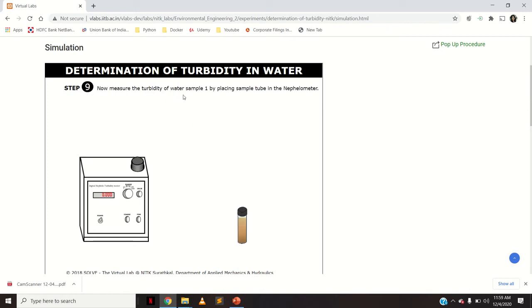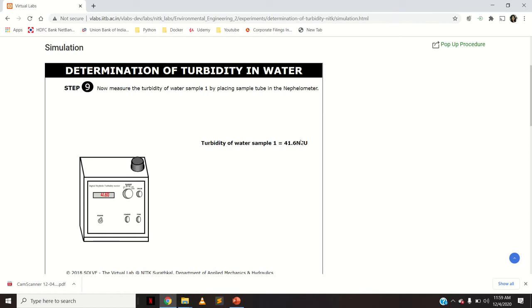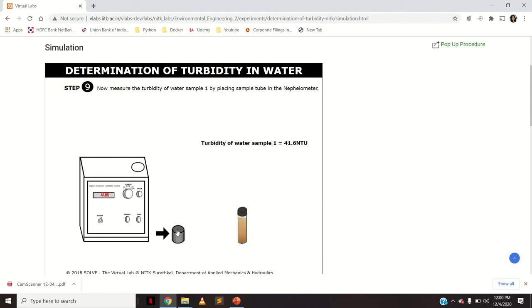Now measure the turbidity of the first water sample by placing the sample tube in the nephelometer. Since the instrument is calibrated with 0 NTU (distilled water) and 100 NTU (standard solution), open the lid, place the sample cell with the first water sample, and close the lid. The digital reading shows a turbidity of 41.6 NTU for the first water sample.